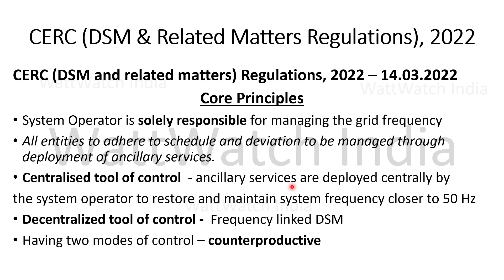The centralized one is having a global effect on the grid, whereas the decentralized one is first of all not in direct control of the operator, because some utilities or generators may choose to support the grid. Some may just not choose to do it. Some may just choose to follow their schedule. In addition to that, the local action of the generator or the utility to choose to support the grid is temporal in nature. It is only spatial, only up to a certain extent. So having a centralized tool and a decentralized tool all at the same time may not send the correct signals and may be counterproductive. It is basically an additional layer which is not exactly supporting your cause. So these principles totally envisage that the centralized tool of control, which is the ancillary service deployment through the system operator, will be the only tool that will be used to control the grid frequency.